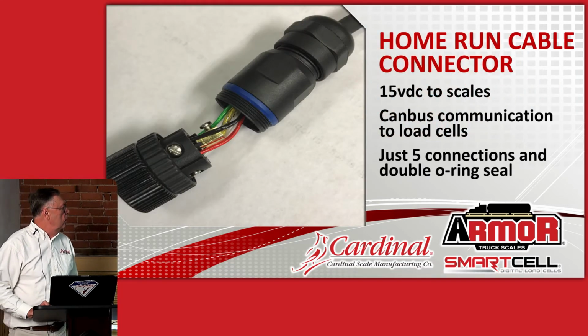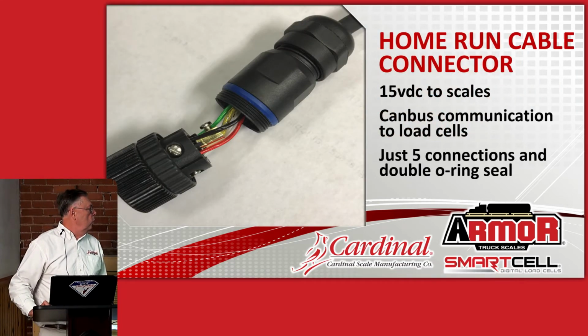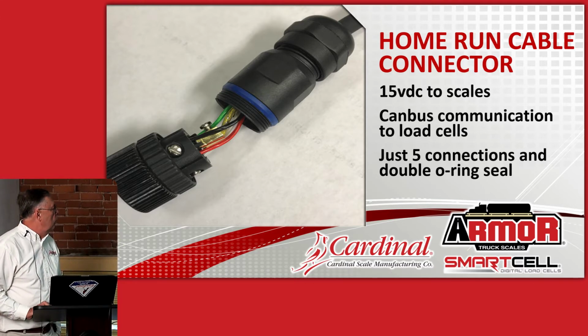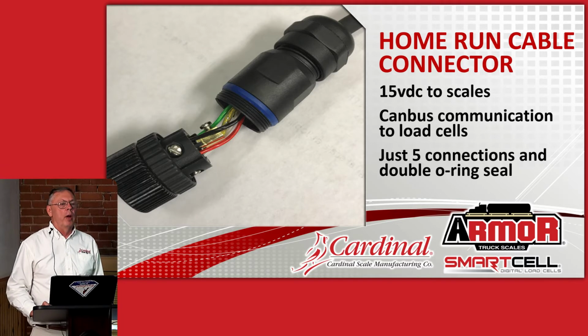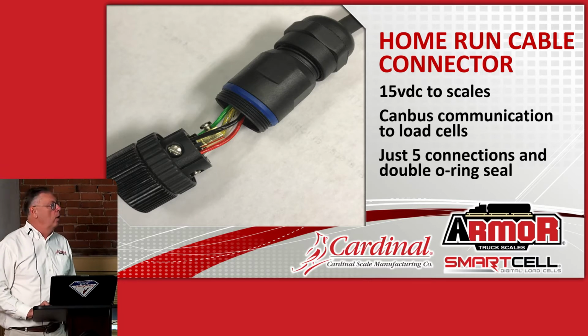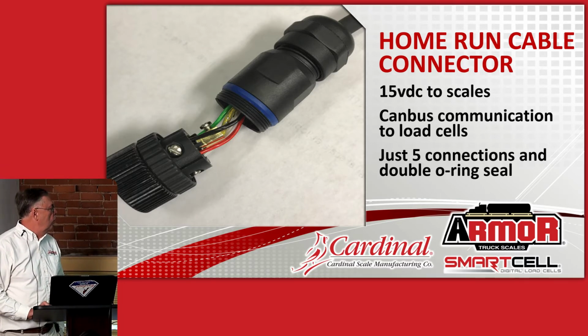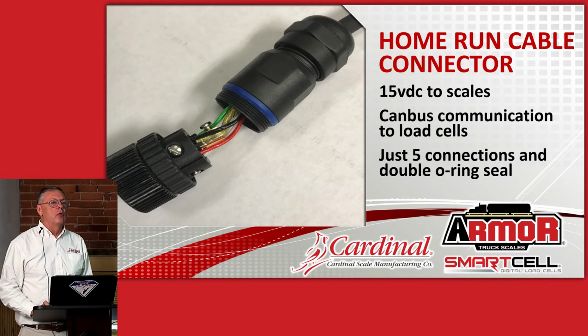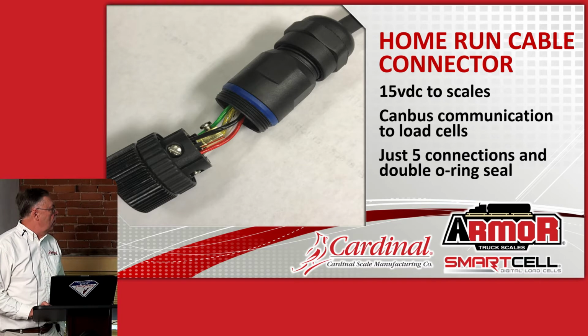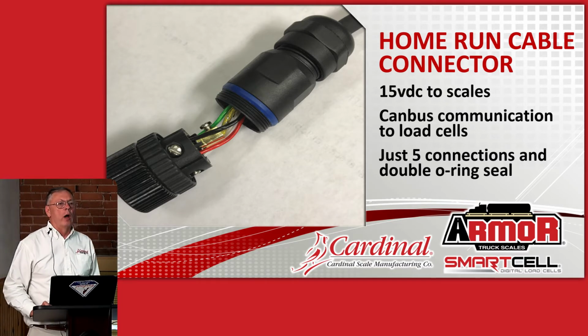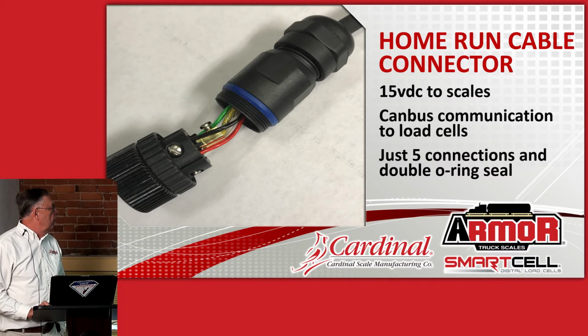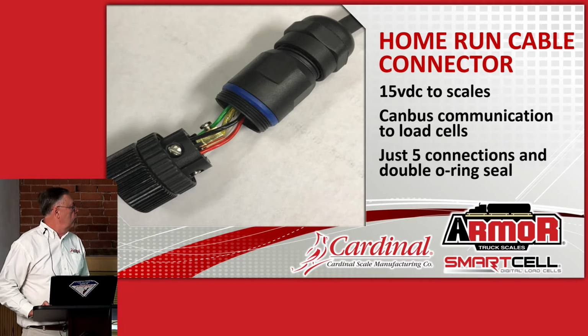This is the home run cable connector. This is one of the 2 places that the customer does have to make some connections. You've got to connect a pair of wires for 15 volts, plus and minus DC, to run the load cells. And then the other 2 wires, the signal wires, are just a CAN bus loop for CAN high, CAN low. And then there's a shield wire in the center. That connector has got double O-ring seals. Those are the only 5 connections that have to be made at the scale.